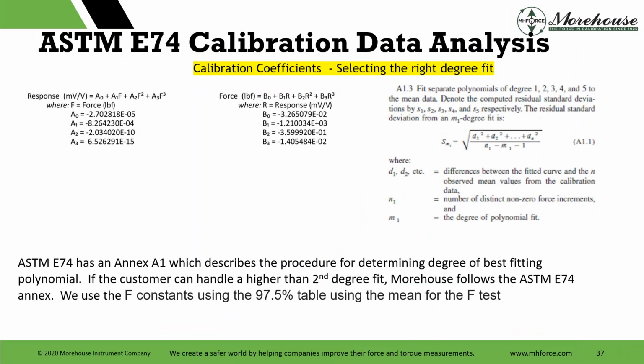And what we do here, selecting the right degree fit, ASTM has an annex. So you say, hey, I have more than 50,000 counts of resolution. How do I select the right degree fit? And that's A1.3 of the annex, which says fit separate polynomials of degree 1, 2, 3, 4, and 5 to the mean data. Denote the computed residual standard deviations by S1, S2, and there's the formula. So really, it has a procedure for determining the degree of best fitting polynomial.